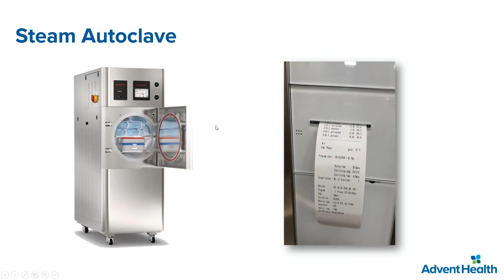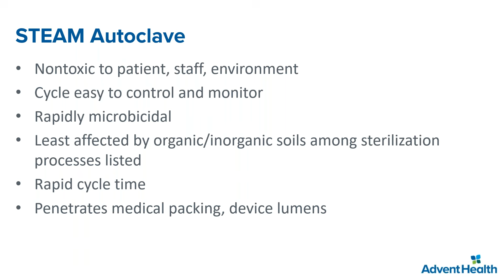The steam autoclave is very good. It's non-toxic to patients. It's what we have used for ages. The cycle is easy to control and monitor. It's very rapidly microbicidal. It's the least affected by organic or inorganic soils among sterilization processes. The cycle time is very fast and it penetrates medical packing and device lumens.